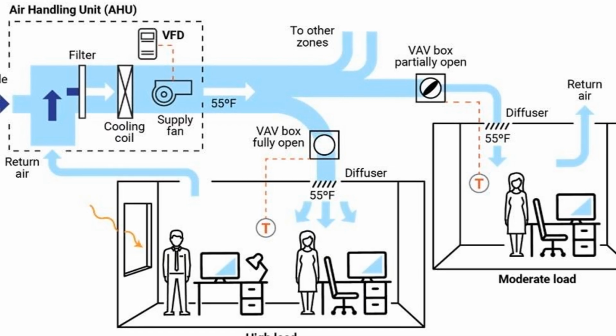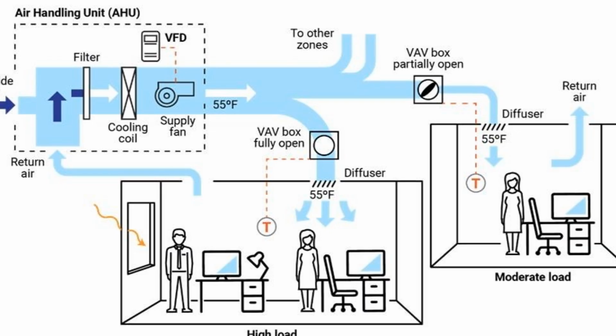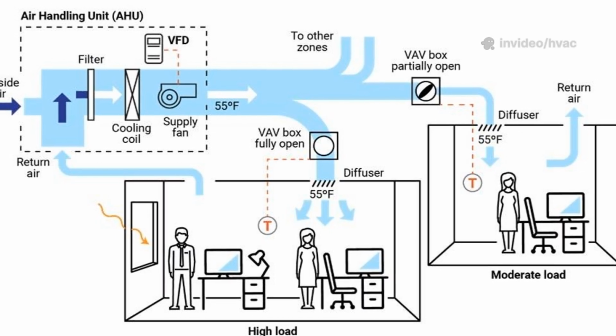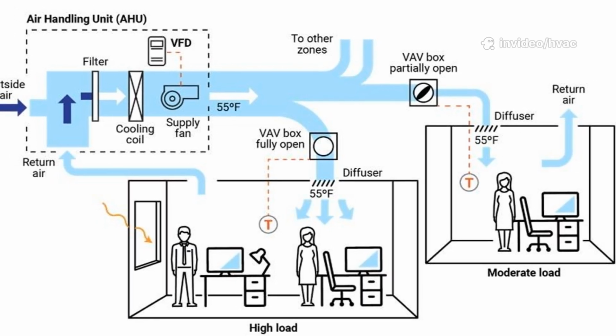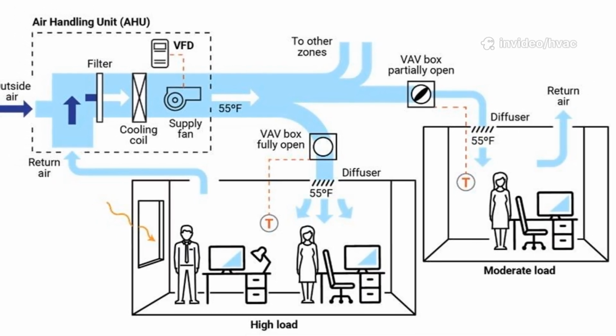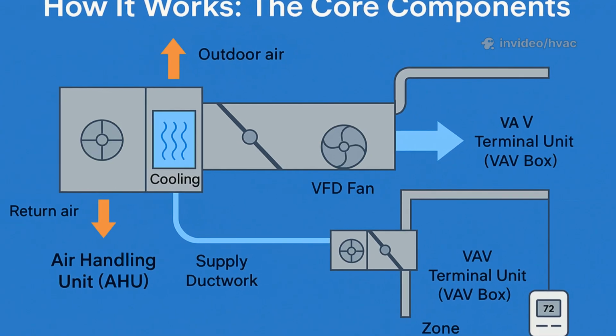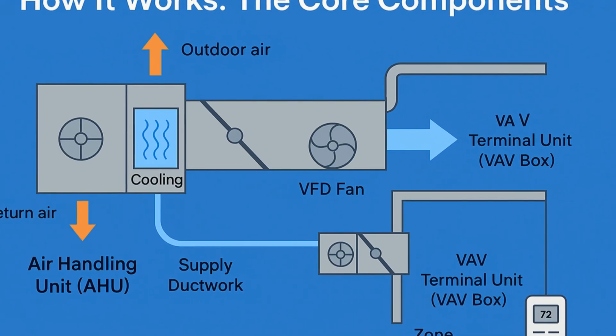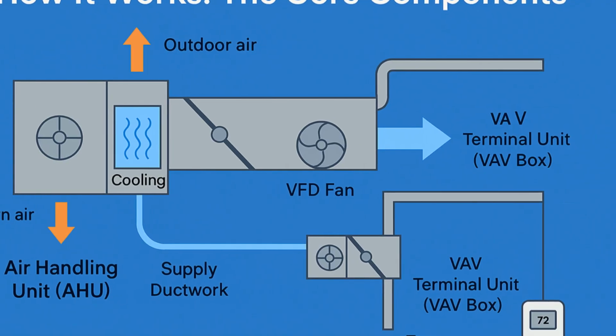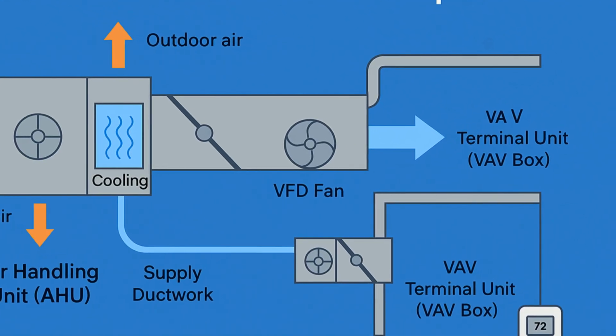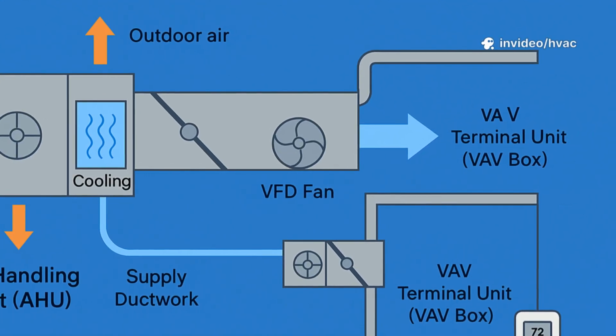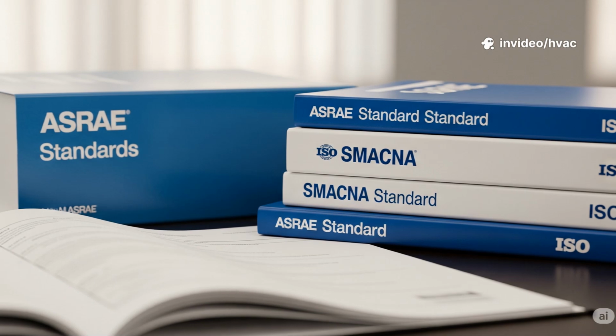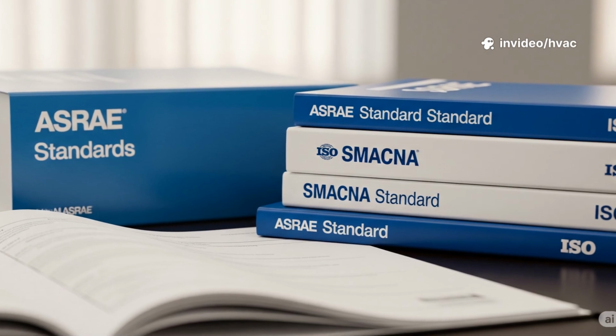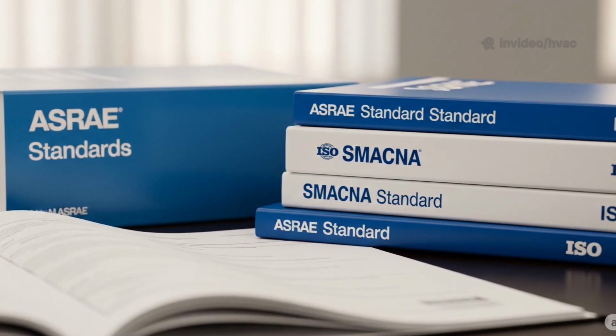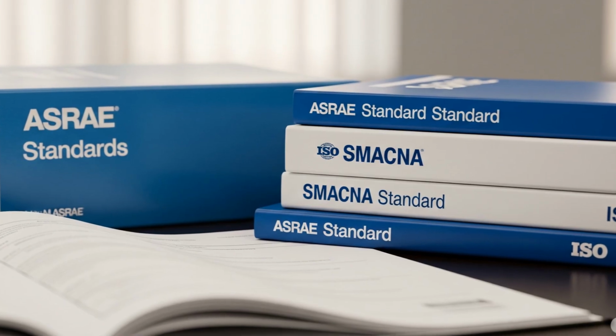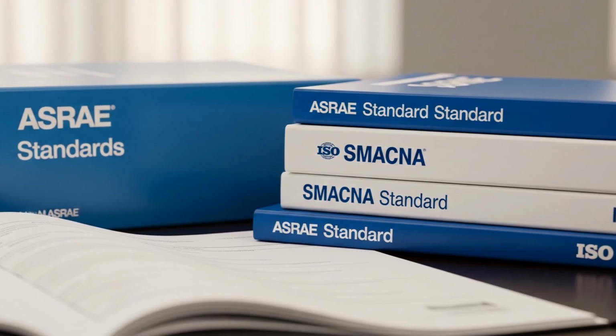When a room starts to warm up, the damper opens wider, letting in more cool air. When the room reaches the desired temperature, the damper closes, conserving energy and maintaining comfort. Once a zone reaches its set point, the VAV box reduces airflow gradually. However, it doesn't shut off entirely. The damper modulates down to the minimum CFM required for ventilation, maintaining a consistent flow based on ASHRAE guidelines or local code. This ensures air quality and keeps duct static pressure stable. It's a dynamic process that happens quietly and automatically all day long.